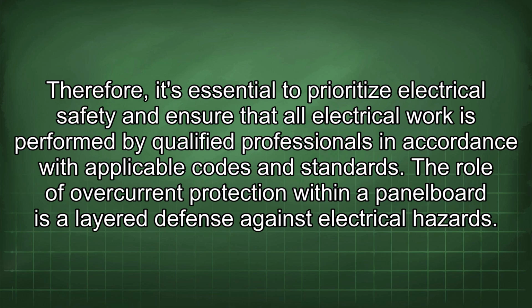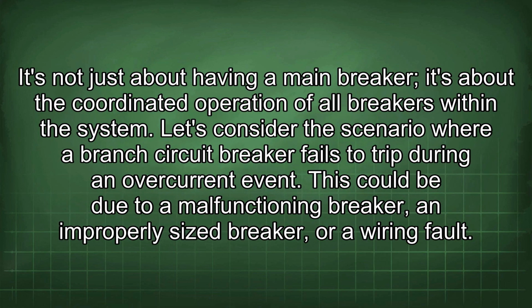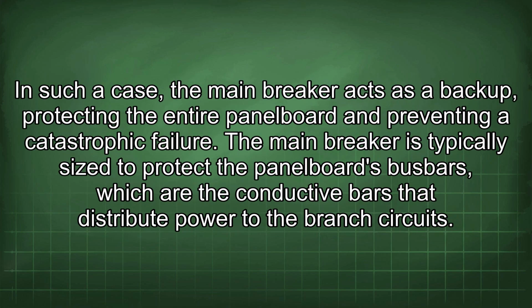The role of overcurrent protection within a panel board is a layered defense against electrical hazards. It's not just about having a main breaker, it's about the coordinated operation of all breakers within the system. Let's consider the scenario where a branch circuit breaker fails to trip during an overcurrent event. This could be due to a malfunctioning breaker, an improperly sized breaker, or a wiring fault. In such a case, the main breaker acts as a backup, protecting the entire panel board and preventing a catastrophic failure. The main breaker is typically sized to protect the panel board's busbars, which are the conductive bars that distribute power to the branch circuits.